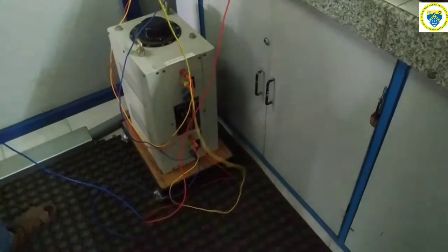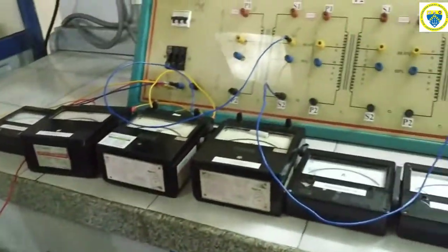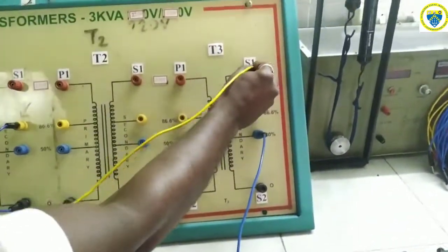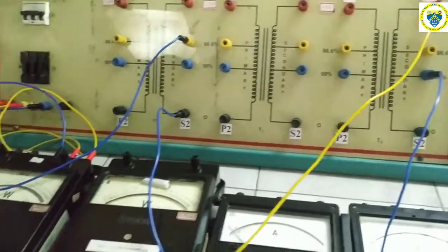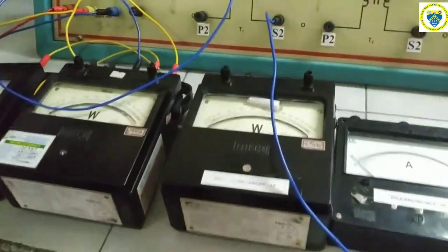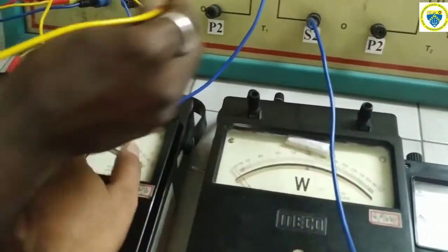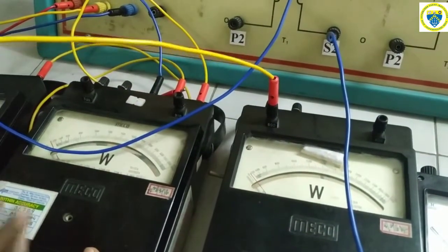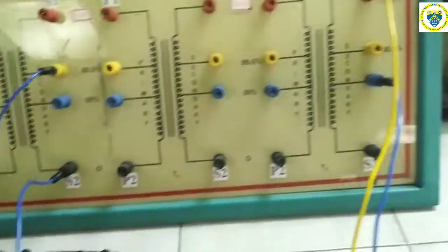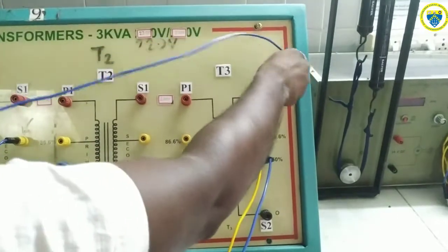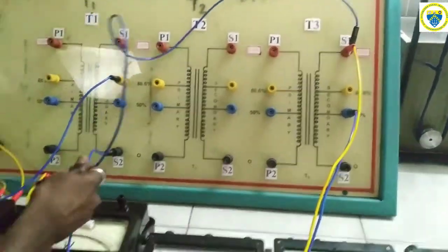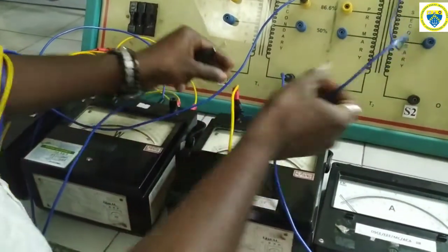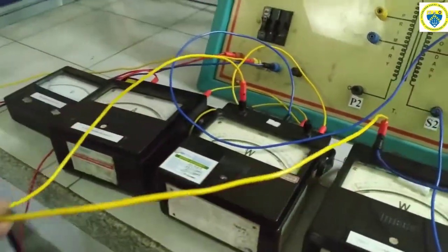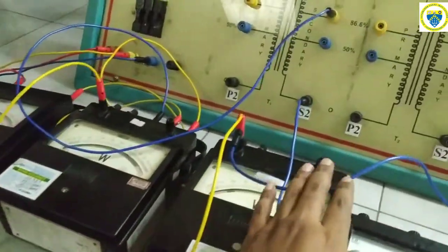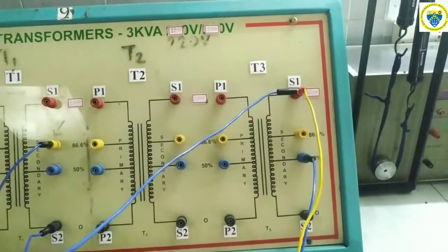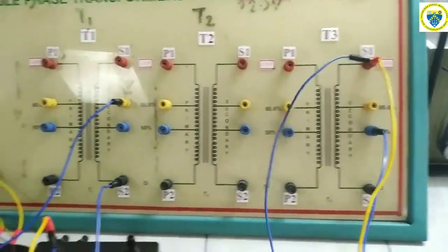Then next from Y phase, it should be given to the S1 terminal of the teaser transformer, and then the V and V of both the wattmeters should be shorted, and one terminal should be given again to S1 of the teaser transformer. So here VV of the wattmeters are shorted. Again one more wire is going to the S1 terminal of the teaser transformer.